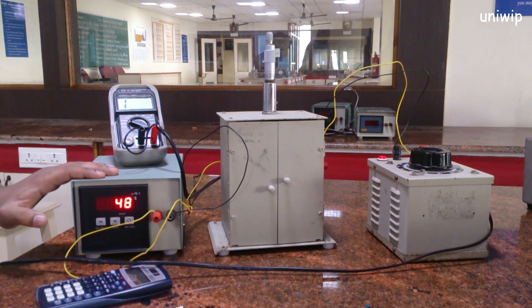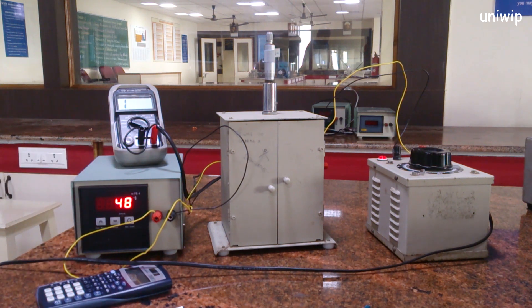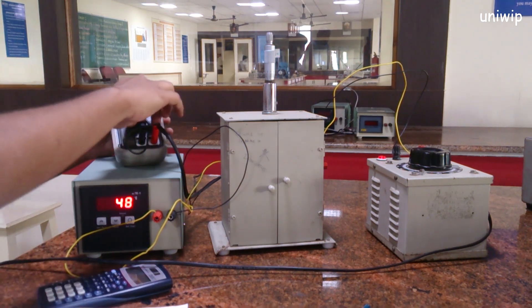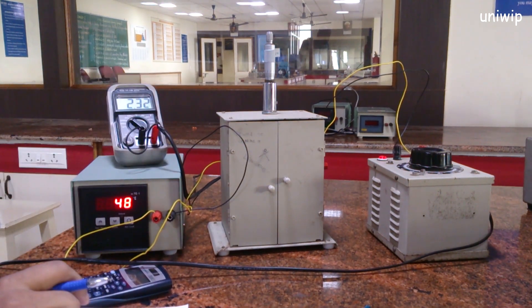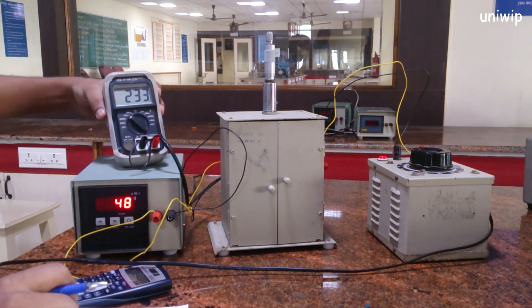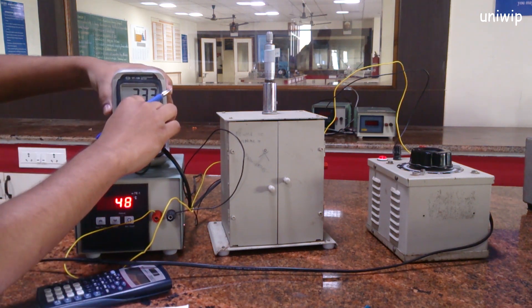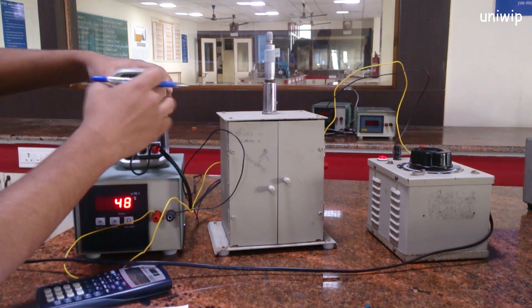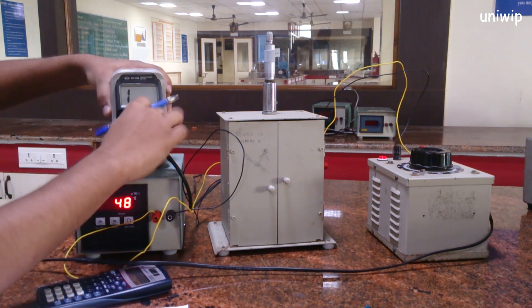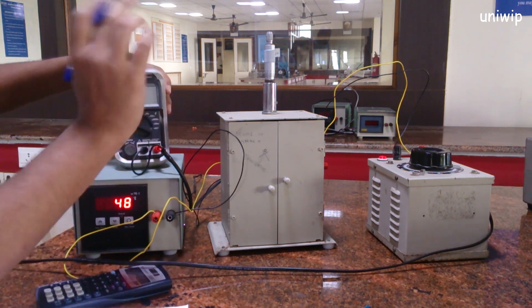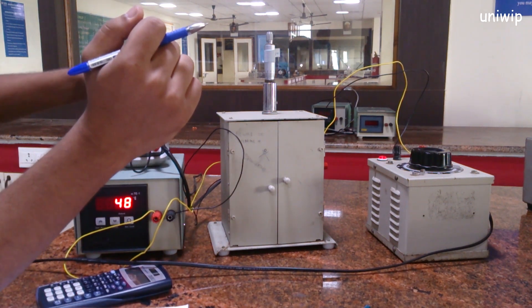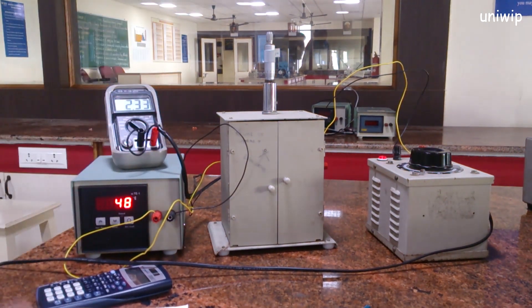Now let's start with switching on all the apparatus. Okay, now as you can see my initial temperature reading is 48. Alright, let's start with 48. Let's take the measurement first for 48. You're gonna be setting it to, yes, you're gonna be setting it into 20 nanoF. The measurement should be 20 nanoF because when I keep it at 200, my reading was 1. That means the output that I was getting was not enough in this device to source. So you gotta make sure that you put the device in the optimum status that you can see the output. That is 20 nanoF. Alright, so let's start off with the experiment.